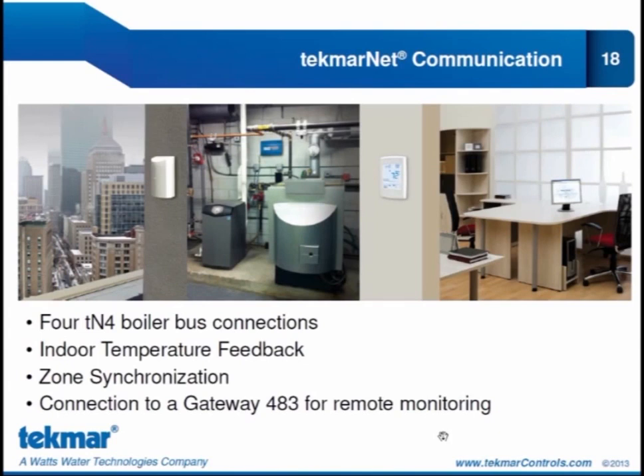tekmarNet communication allows us to provide indoor temperature feedback. Now we can connect tekmarNet devices to 4 TN4 buses. There are 4 TN4 buses on the 284 boiler control. And we have the same rules about the number of devices per bus. It's 24 devices per bus. What that does is give us a total of 96 possible devices on the tekmarNet network. Now, all of these are the boiler bus. It's all boiler bus water temperature. Just to be clear of that, there is no mixing available on the 284.